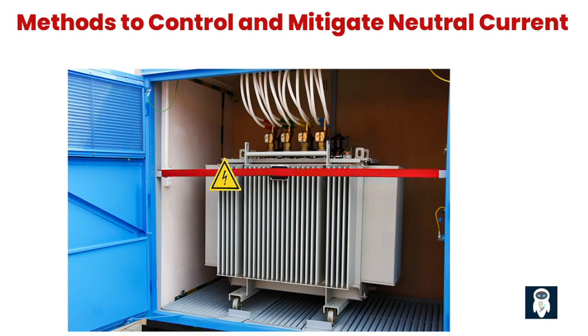2. Neutral current transformers (NCTs) are specifically designed to measure and monitor neutral currents. By installing NCTs, it becomes easier to detect excessive neutral currents, take corrective measures, and prevent potential problems in the electrical system. 3. Resistor grounding and compensation methods involve the use of resistors to limit the flow of neutral current. By introducing resistance in the neutral grounding path, the excessive neutral current can be reduced, ensuring a balanced system and protecting equipment from potential damage.